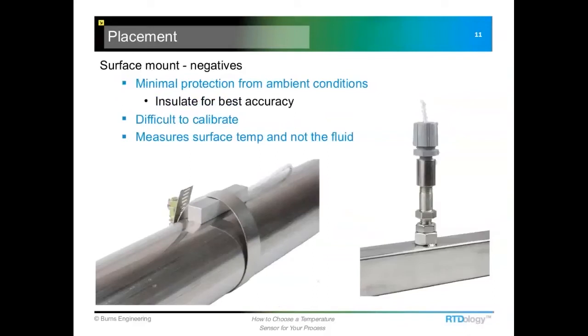Some of the negative aspects: like I said, we need to insulate over the top just to keep the ambient conditions from affecting the measurement. Most of these are odd constructions compared to a typical cylindrical type sensor, so they're difficult to calibrate. You almost have to have an oil bath or some kind of liquid bath to be able to calibrate these. And finally, we're measuring the surface temperature of the pipe or a plate or whatever it might be, rather than the actual fluid inside the pipe or whatever's underneath, like in a flat plate type application.